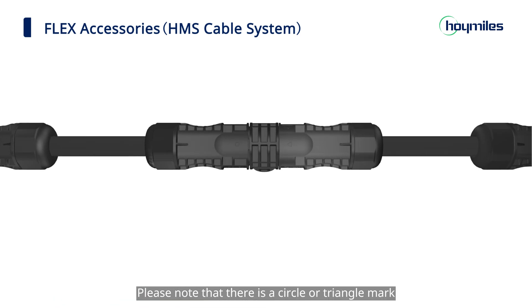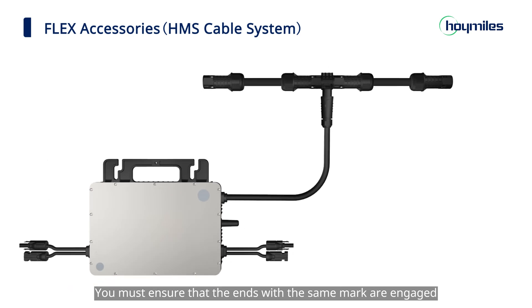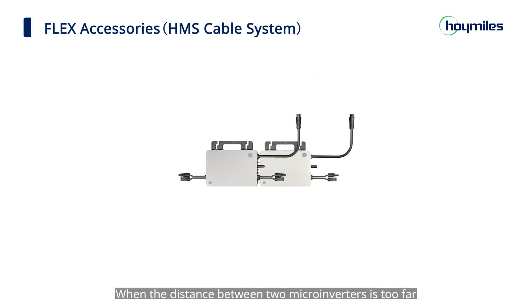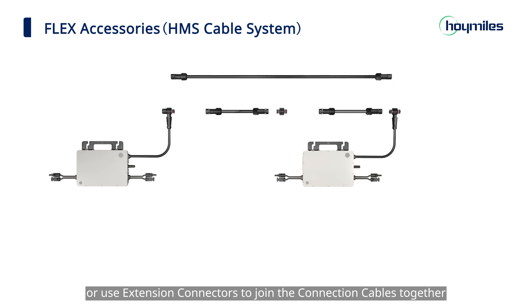Please note that there is a circle or triangle mark on each end of trunk connectors and connection cables. You must ensure that the ends with the same mark are engaged. Any unused ports should be covered with the HMS sealing cap. When the distance between two microinverters is too far, you can either choose a longer connection cable or use extension connectors to join the connection cables together.